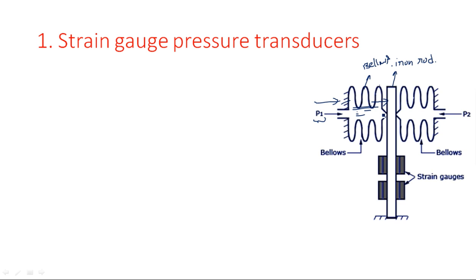So the iron rod will have stretching towards the right side direction. Because of this bending, the strain gauges connected on this iron rod will have resistance change due to compression and elongation. When we apply pressure P1 from left to right, this bellow has influence on the iron rod and the iron rod bends in the right-hand direction. These two strain gauges on the right-hand side will be compressed.